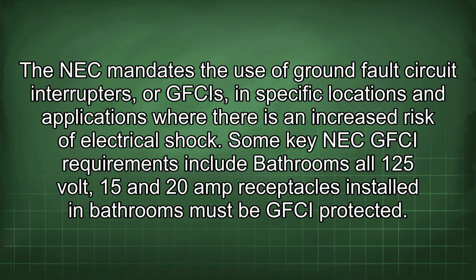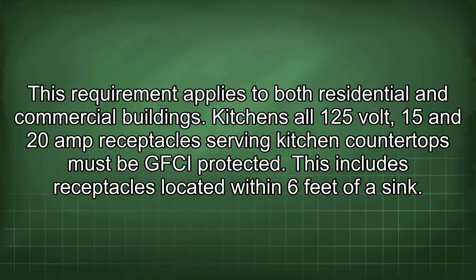NEC GFCI requirements include: Bathrooms, all 125 volt, 15 and 20 amp receptacles installed in bathrooms must be GFCI protected. This requirement applies to both residential and commercial buildings. Kitchens, all 125 volt, 15 and 20 amp receptacles serving kitchen countertops must be GFCI protected. This includes receptacles located within 6 feet of a sink.